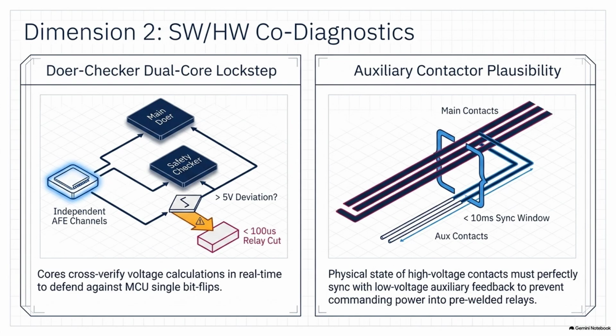There's absolutely no time to argue. The document outlines that a dedicated independent silicon module, often called the Safety Management Unit, or FCCU, steps in. It physically bypasses the software entirely. In under 100 microseconds, it severs the low-voltage power supply feeding the physical relay drive circuits. Wow. It doesn't ask the software to gracefully shut down. It reaches over and physically unplugs the power, steering the hardware. It acts as an absolute hardware override. By cutting the drive power, it guarantees the high-voltage contactors drop open and default to a safe, unpowered state. It completely neutralizes the risk of a software control escape caused by a stray cosmic ray.